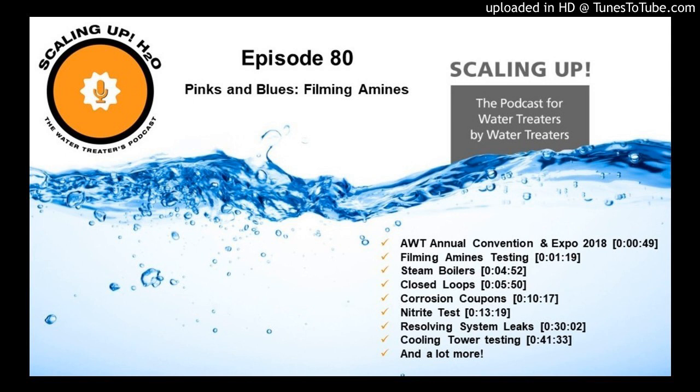But of course, with that comes a higher price tag. So it was at least 4 times more expensive than the product that I was using before. And it was a closed loop system. And if you look at the corrosion coupon results side by side, which you can on my show notes page, you will see that they're not that much better. I mean, we're talking about thousandths of a point when we're talking about mils per year. By the way, corrosion coupons are measured in mils per year. What the heck is a mils per year? Well, it's 1/1000th of an inch lost in metal per year. So now you know what a mils per year is.